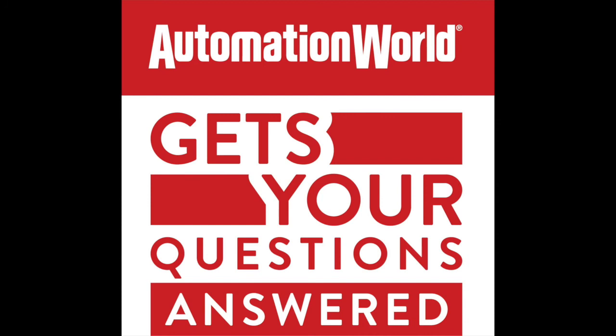I think they got to first be open to the fact that in most situations, you may need both. You can't just say, I'm going to do wired or wireless, because you're going to get into weird situations where one's going to be better than the other. I follow some kind of guidelines. I use wireless mainly when wiring is hard. I got really long leads, or some other issue. Maybe I got a vent up on top of a roof, or a truck door coming in. I just got one sensor up on the top to tell when the door's all the way open. That's really nice for wireless because of the cost savings. You don't have to run the conduit, the cable, get somebody. It just makes it a lot simpler.